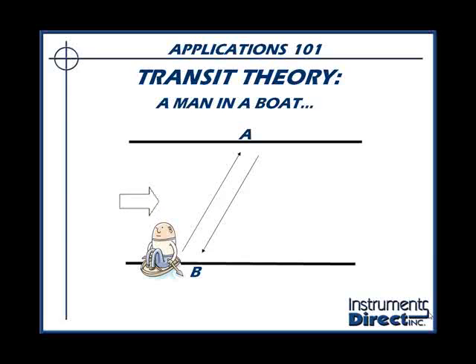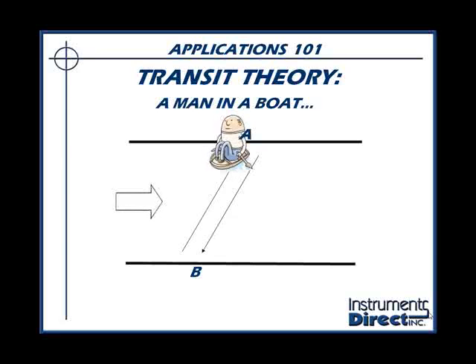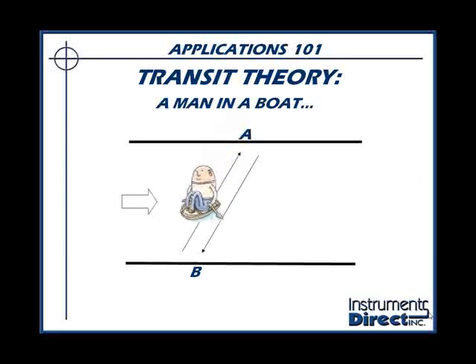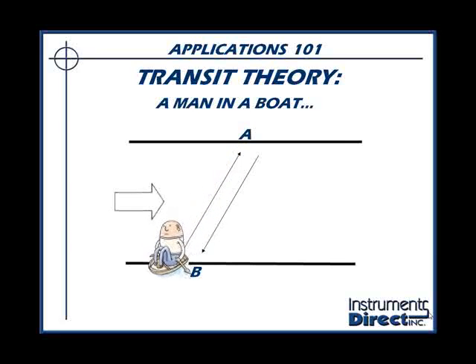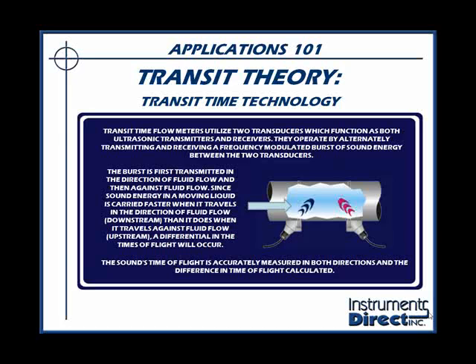same point. So from this we've learned that because of the current of the flow, it takes him a certain period of time. When he comes back against the current, it takes him a longer period of time. The faster the flow rate, the greater the differential from the time he goes across the river to the time he comes back, because he has to go against the current. Using this in mind with an installation of an ultrasonic transit time flow meter.